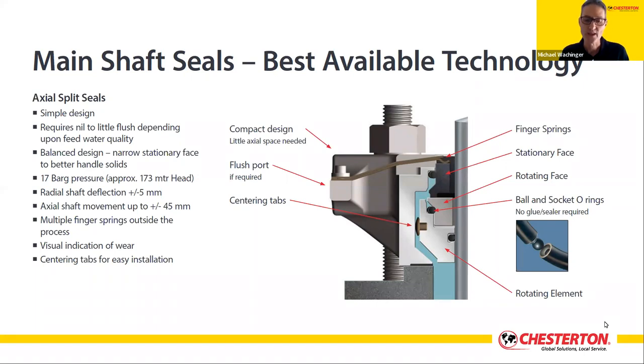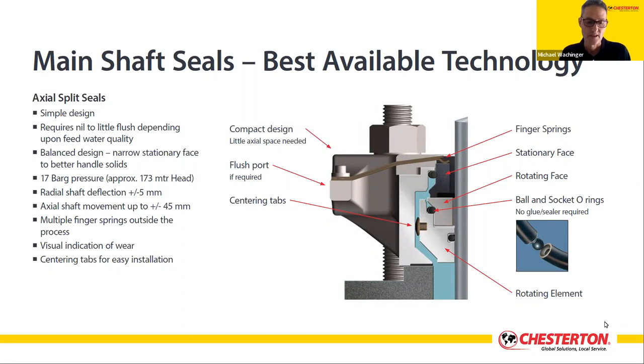Because the seal face designs are actually split-assembled, the rotor element cannot score the main shaft sleeve. Due to their wide face design, they allow for larger radial movement, which can be common in turbine shaft runouts, particularly when equipment has been running for many hours. Then with long finger springs, axial movements such as hydraulic lifts can be compensated for, allowing sealing to be maintained throughout the various hydrodynamic effects during running, and particularly with startup or slow running processes.